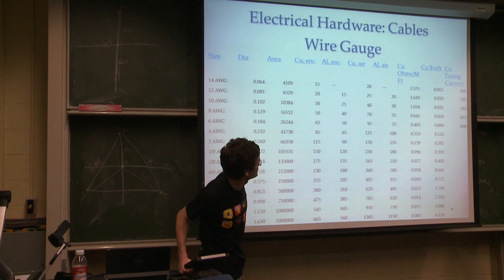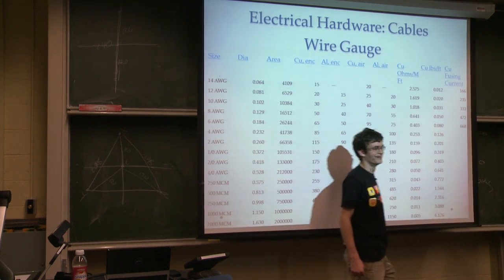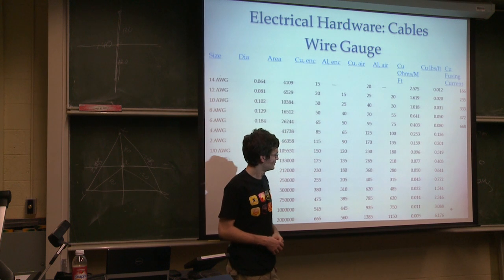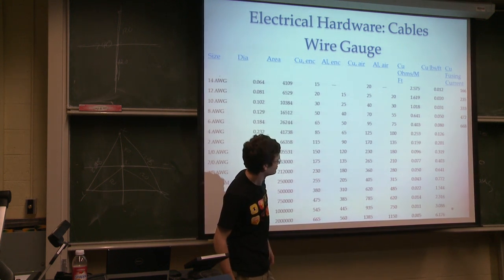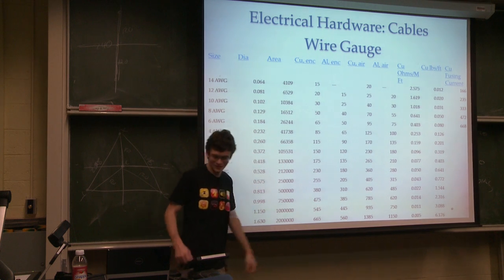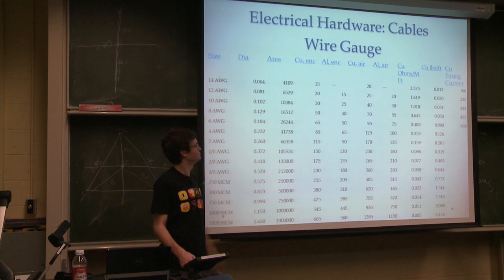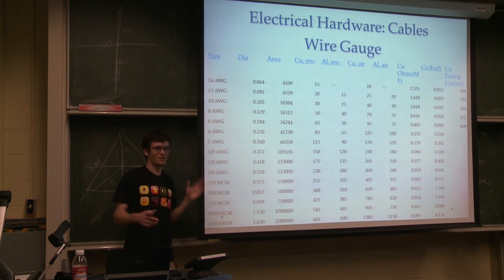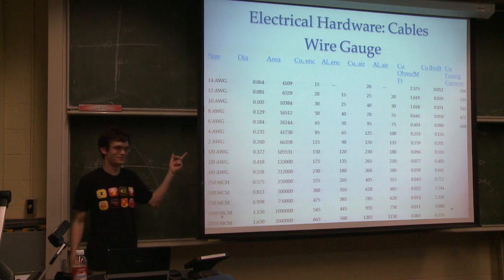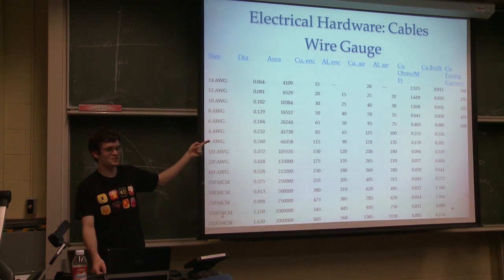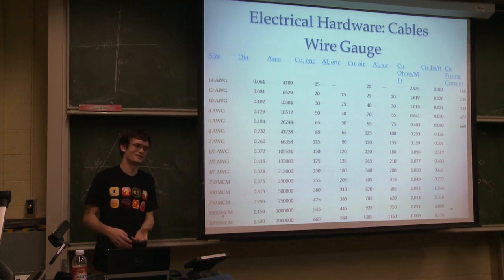Awesome. I can see they stopped carrying at one point. Well, that's more than you can carry on 2,000 MCM cable. So you probably aren't going to use anything bigger than 6 gauge as a fuse. Ever. Okay. And so everyone get why it's important? With high currents, they get hotter, they'll eventually explode. Does it make sense why you can only run so many amps through certain cables?